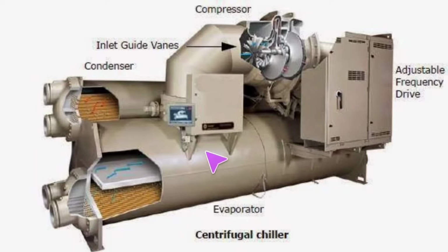And what can happen is if that plate's not there to distribute it, it will cause the refrigerant to collect or pool more heavily right here in this one spot, and you won't get an even distribution or evaporation throughout the entire barrel, which then heavily impacts efficiency. It impacts everything. It's not what we want. It's not what we're looking for. So anyway, this distribution plate allows that, and really all it is is just a screen mesh. I do have some teardown videos I've done where I've shown what that mesh looks like. So if you can go check those out, see what they physically look like in person if you've never seen one.